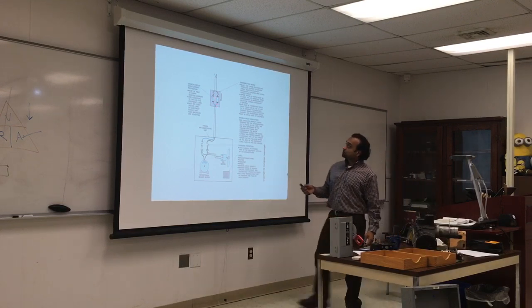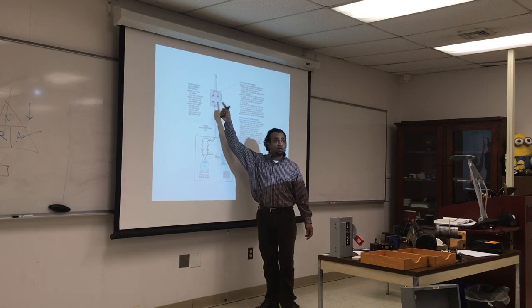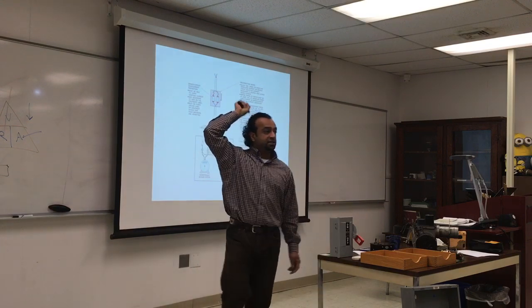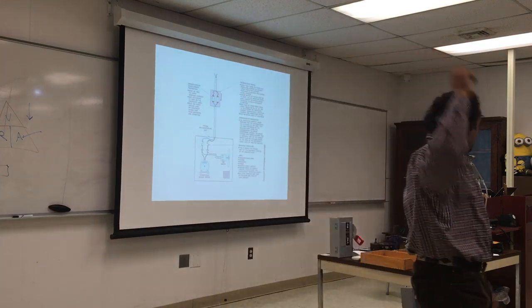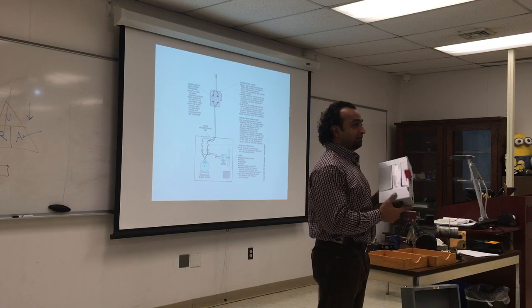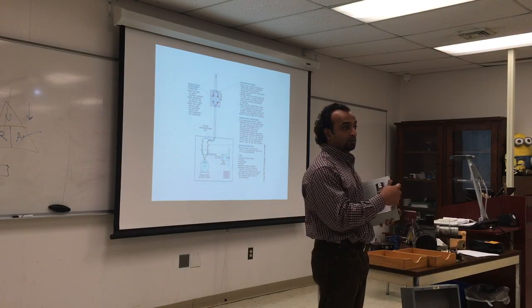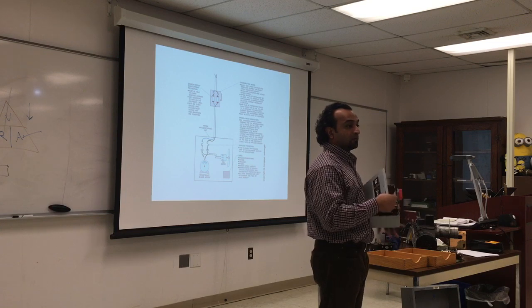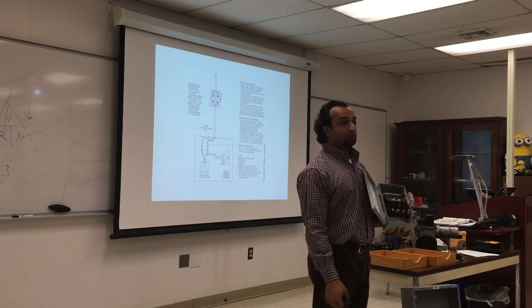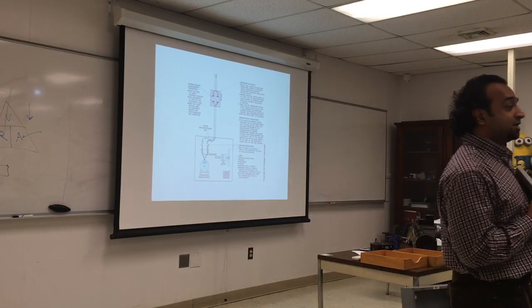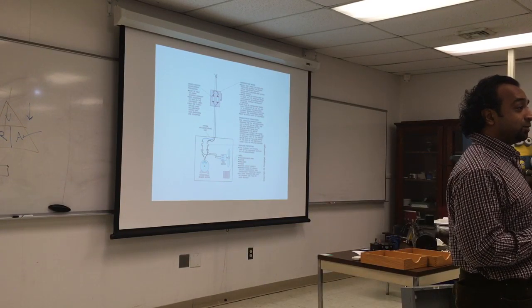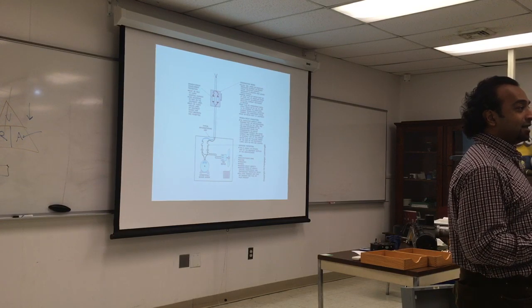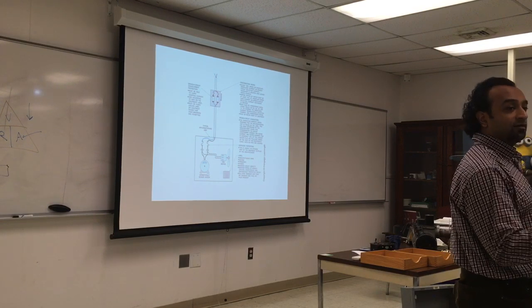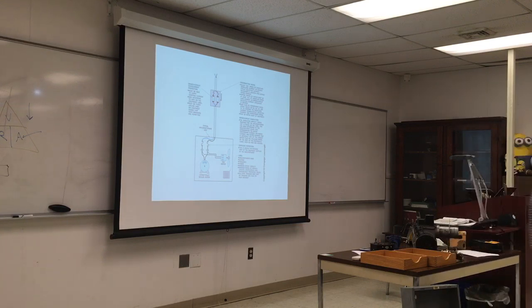Again, check your fuses. Many times you will go to an AC unit outside, look at a three-phase connection, and one of the phases is gone. So you can check the voltage on each one of them, and probably Bill is going to have you do troubleshooting on one of those ACs next semester. One of the things we do is put a bad fuse in there for you to check. First, turn it off, then take the fuses out. There's a tool you use to take the fuses out. Do not use your fingers or your hand, in case there's voltage. You take it out and you check the fuse.